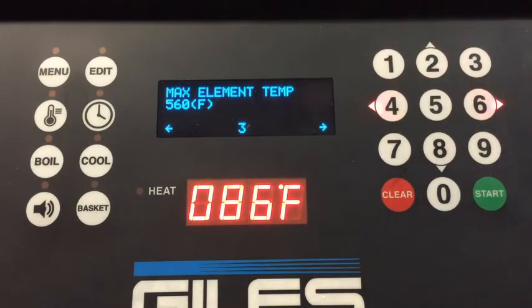The maximum element temperature, 560 degrees. What that is: you've got an element sensor over on the left side of that fry vat, and that element sensor is looking at the temperature of the actual heat element, not the oil, but the heat element. And at 560 degrees, it's going to shut that heat element down because it knows there's no oil in there. If there's oil in there, it'll never get to that temperature.